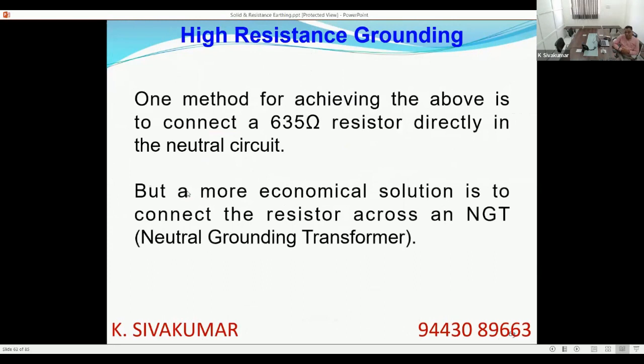Now, one method is to directly provide a 635 ohm resistor rated for 6.35 kV, directly in the neutral circuit. This is again a costly affair. 635 ohm is a very high resistance value, and also it should be insulated for 6.35 kV.